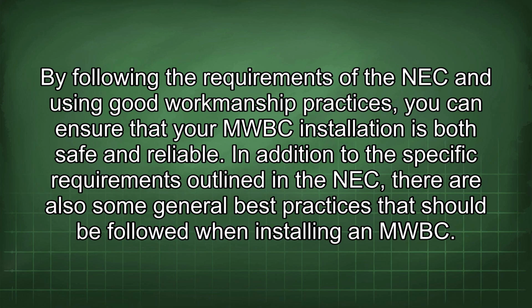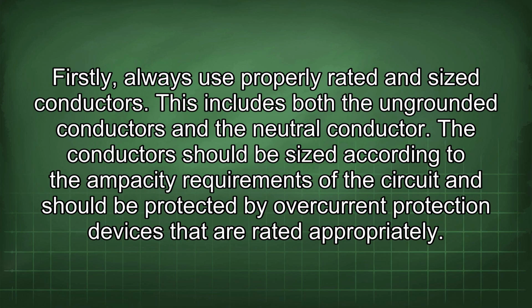In addition to the specific requirements outlined in the NEC, there are also some general best practices that should be followed when installing an MWBC. Firstly, always use properly rated and sized conductors. This includes both the ungrounded conductors and the neutral conductor. The conductors should be sized according to the ampacity requirements of the circuit and should be protected by overcurrent protection devices that are rated appropriately.